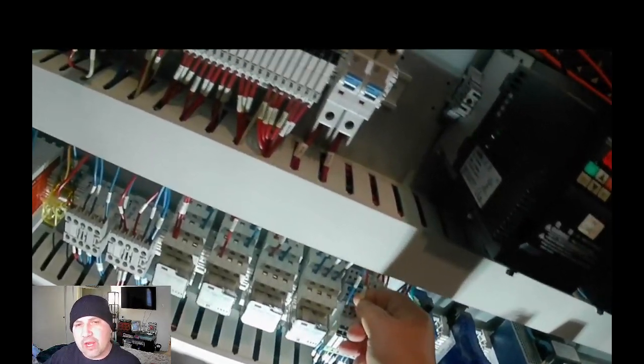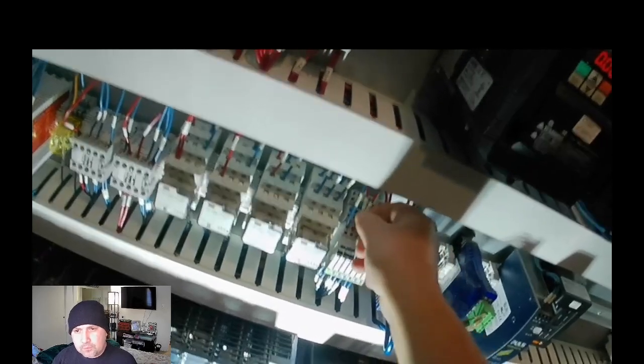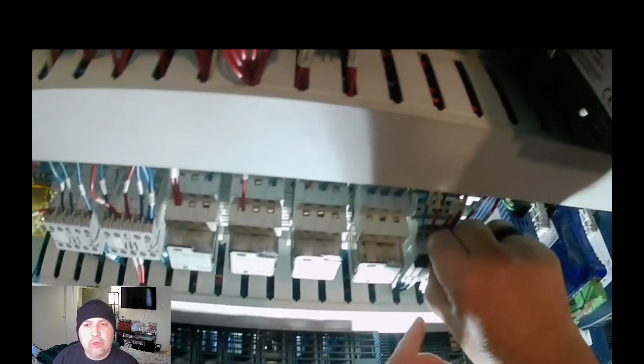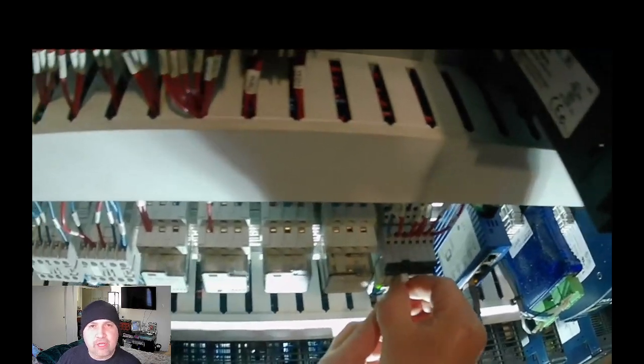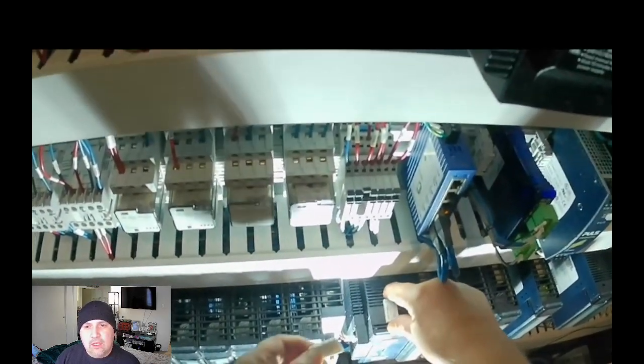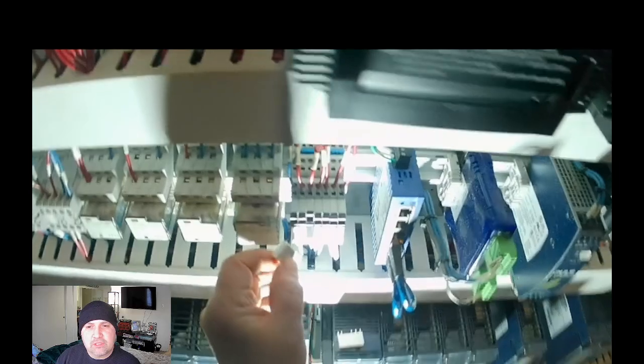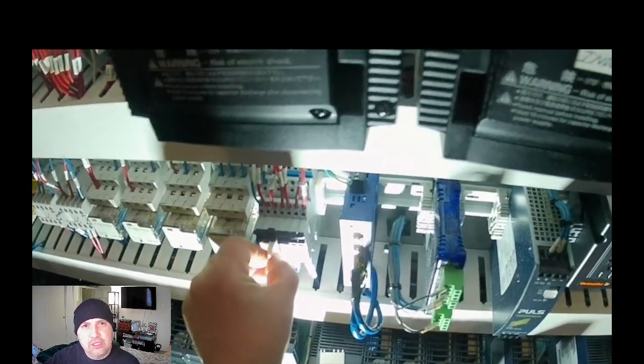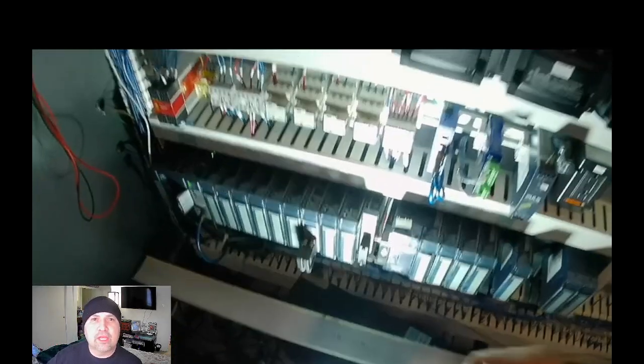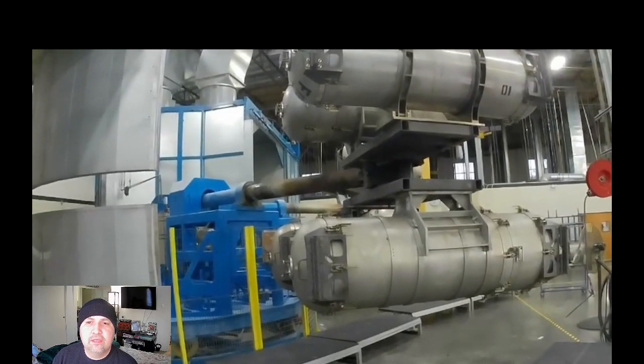But when I got to the brake and I troubleshot the brake itself with my meter, I noticed that the brake wasn't getting any voltage. So I'm going through the wiring that it says leads directly to the brake. And I swapped out some of these relays to see if I got a change, and if I could start sending a signal out to the brake to engage the coil on the brake. But that wasn't having any effect.